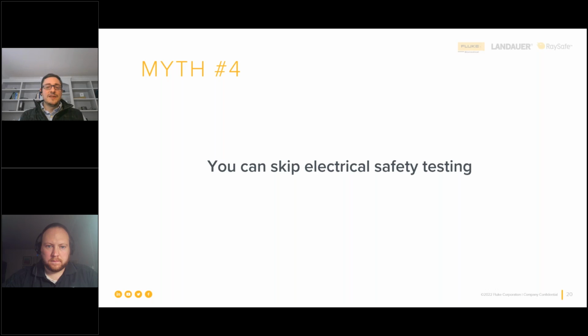I think skipping electrical safety testing, we need to call that into question and think about what you're trying to do when you perform electrical safety testing. The medical device needs to be safe for a patient to be connected to, and safe for a clinician to operate. That's the basis behind the whole thing. Electrical safety testing is valid for a point in time, the point at which you ran the test, and it's likely to remain safe for a period of time after that.